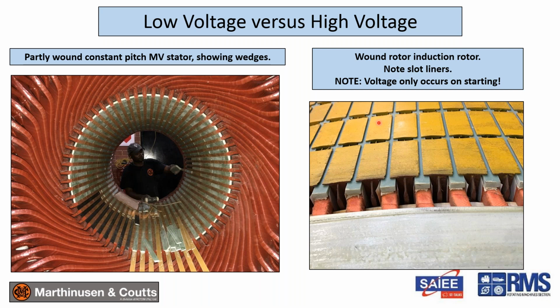Again, I mentioned that voltage applies to rotors in terms of wound rotor induction motors, DC armatures, and wound field synchronous machines. I've already shown you some examples. I've got more to follow of wound field synchronous machines. But here is a wound rotor induction motor rotor, and you can see the slot liner over here. So very similar to low voltage. They have a certain amount of tape on the conductor, and then they use either one or more slot liners.